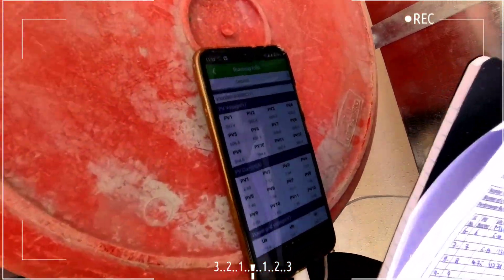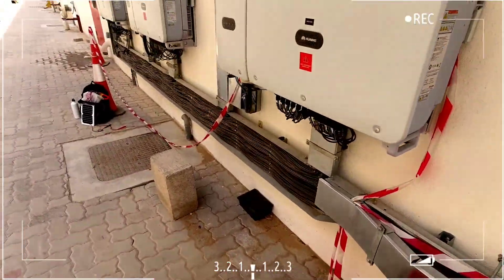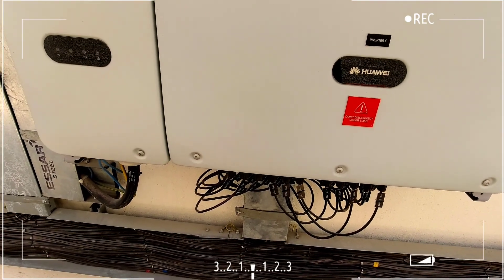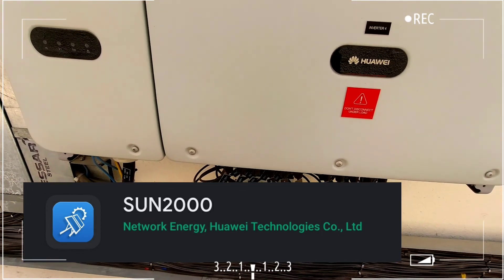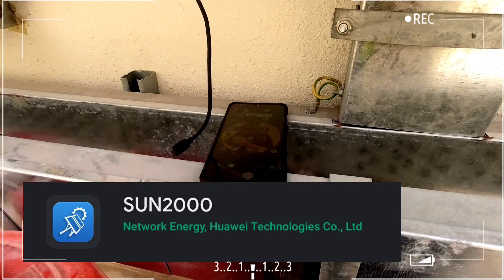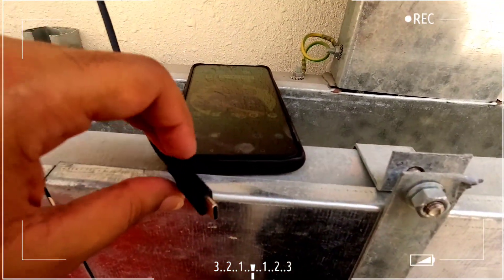Here we are noting down the voltages and current through this USB port. We've connected a cable from the inverter's USB port to the phone. Just in case you don't have a clamp meter, you can note down voltage, current, and generation data from this inverter. Through the SUN2000 mobile app — which is Huawei's inverter app — you can extract data. You need an OTG-supported Android phone with the SUN2000 app pre-installed, an OTG USB cable plugged into the inverter's USB port, and then into your phone.